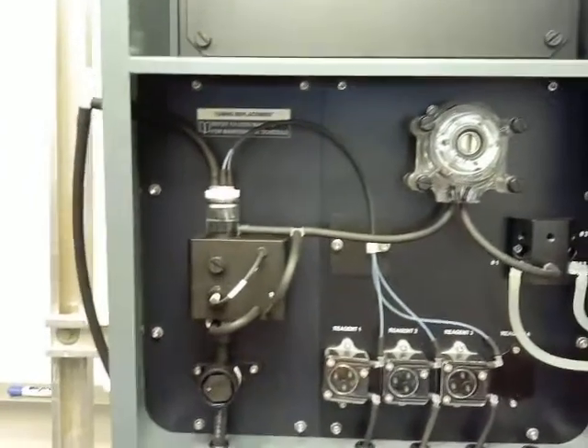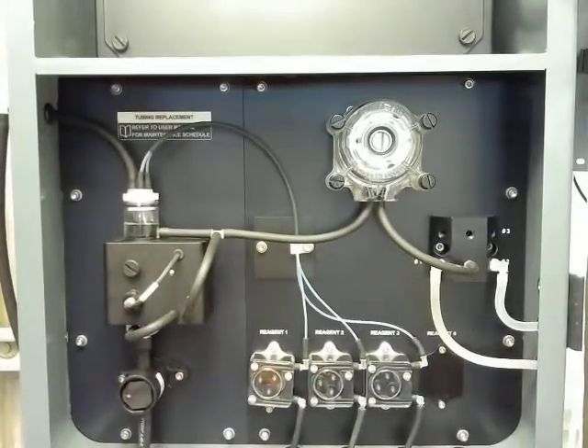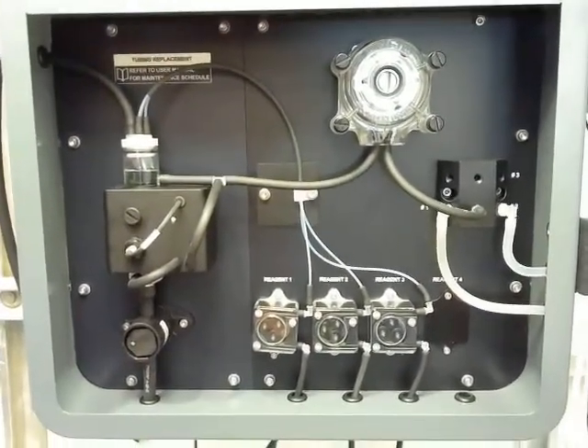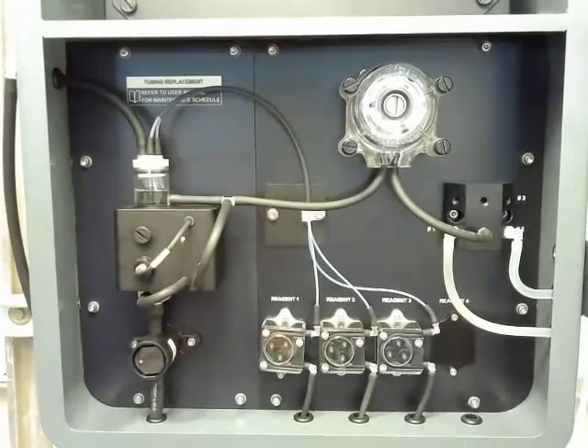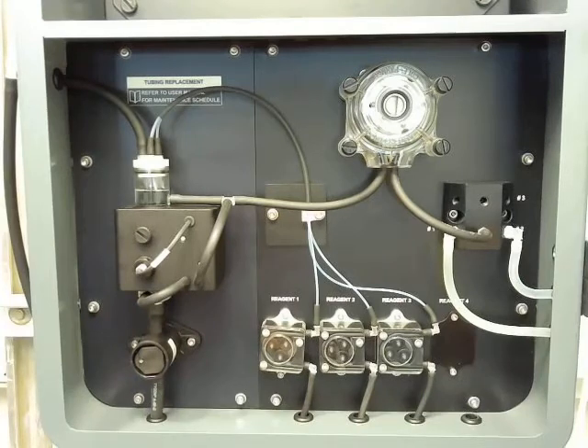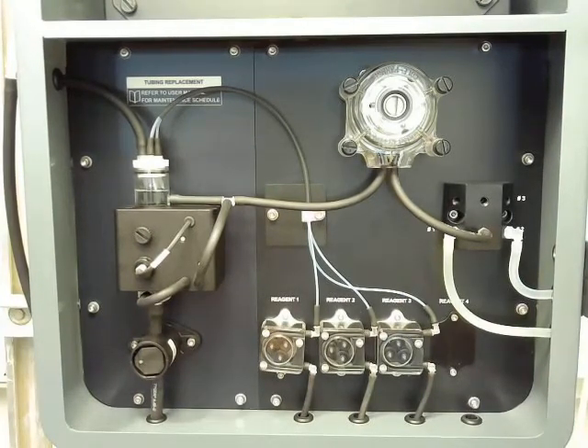So the last part of the quarterly tubing maintenance will be our reagent pumps. The nice thing about peristaltic pumps is that none of your reagents are in contact with really any pump components other than the tubing. You usually get a better lifespan out of your pumps. Obviously, a little more maintenance intensive, but again, once we have the tubing replaced, that's the only thing in contact with some of the reagents that can be a little hazardous and corrosive at times.